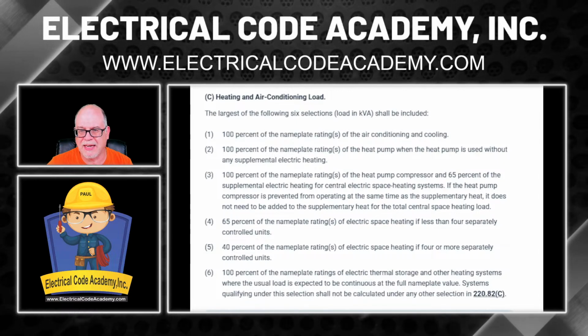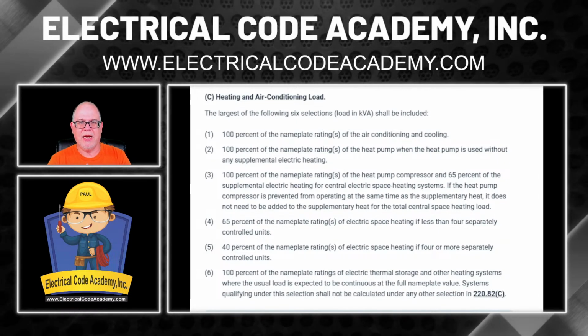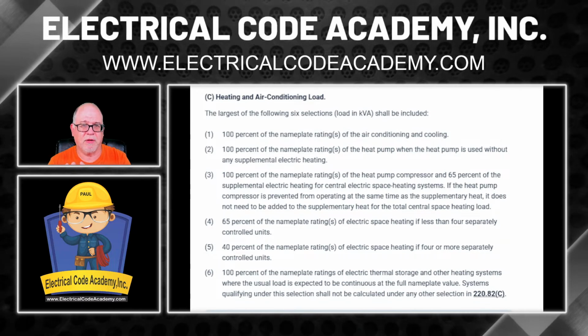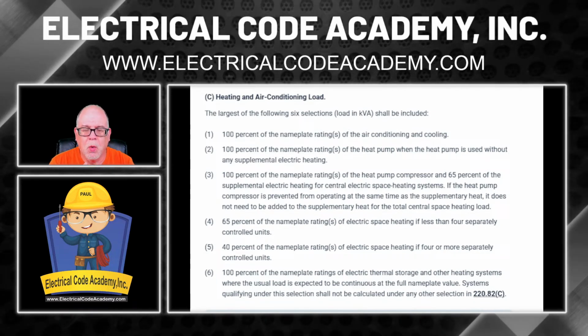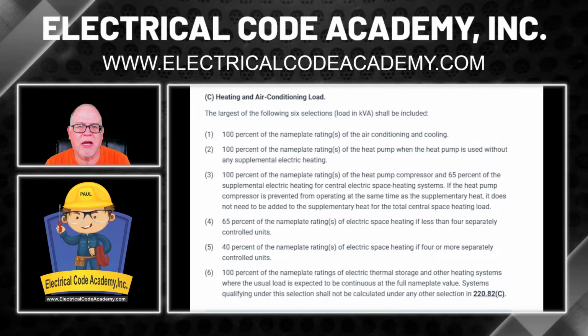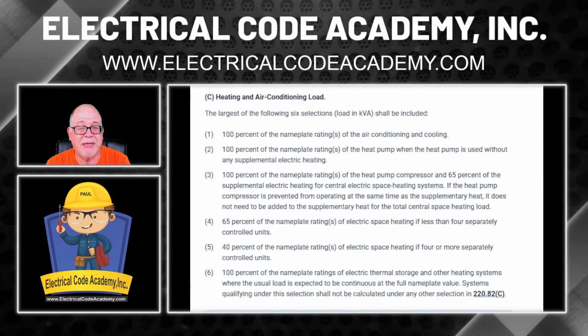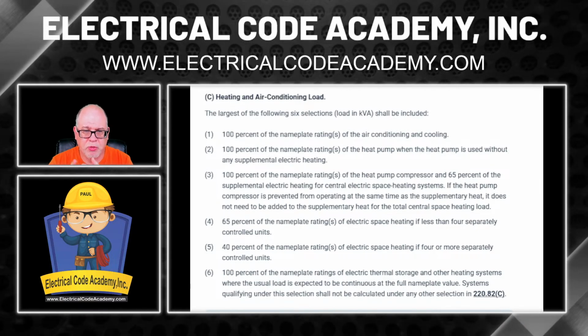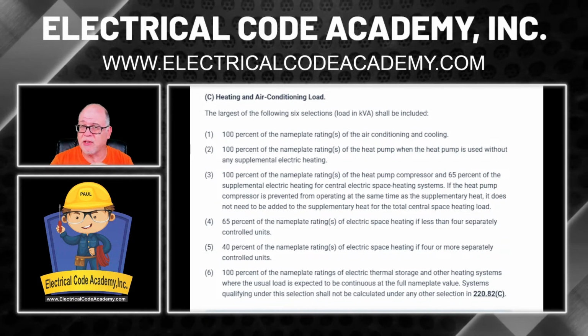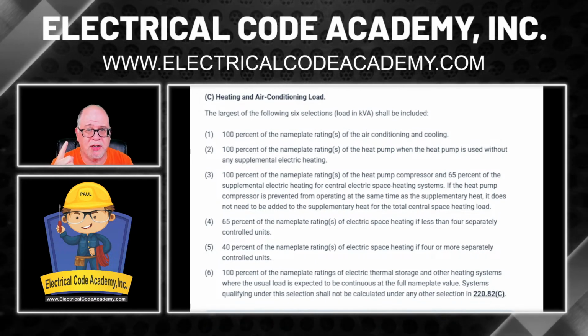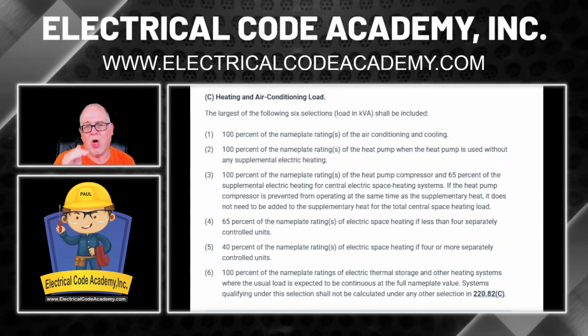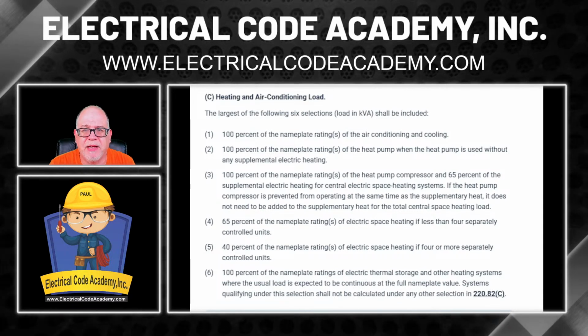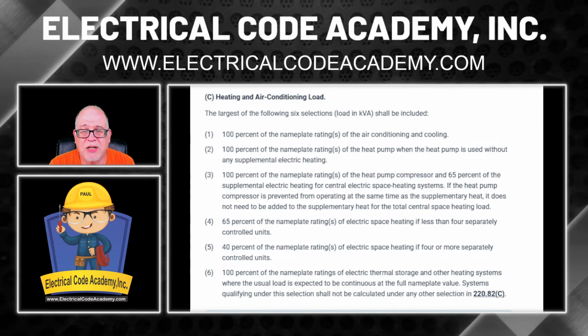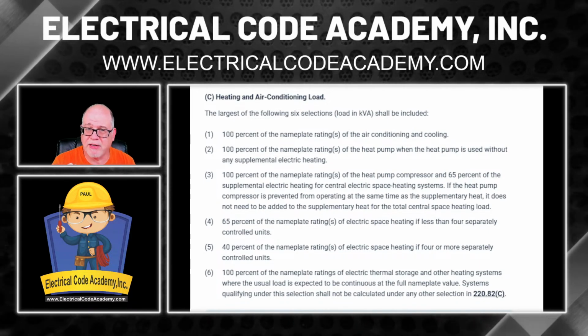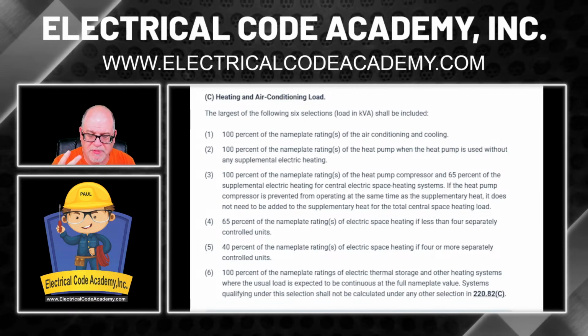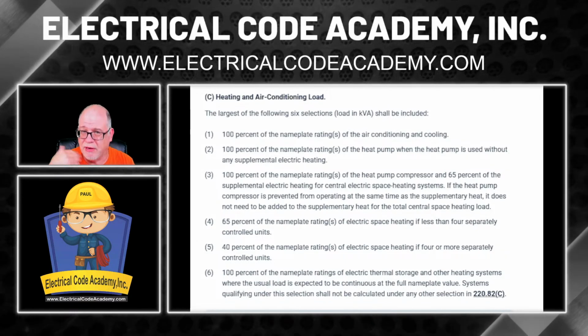Here we've got the heating and air conditioning, and it's broken down into 6 pieces. It says the largest of the following 6 selections shall be included. Well, there's 1, 2, 3, 4, 5, 6. We're only going to use 2 of these. Obviously, one's going to deal with air conditioning, and the other is going to deal with the heat. Number 1 on this list says 100% of the nameplate ratings of air conditioning and cooling. We already know what our air conditioning is. We had 2 of them at 10.5 amps and 3 of them at 7.2 amps.